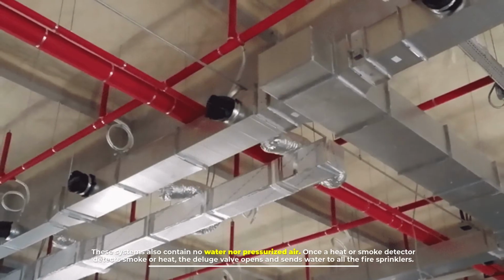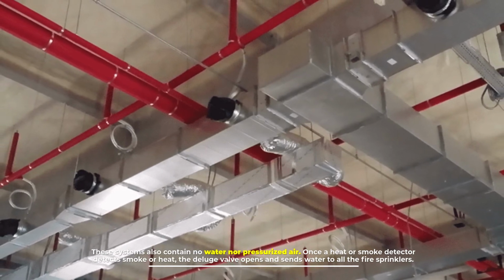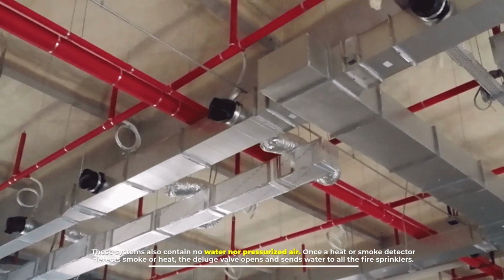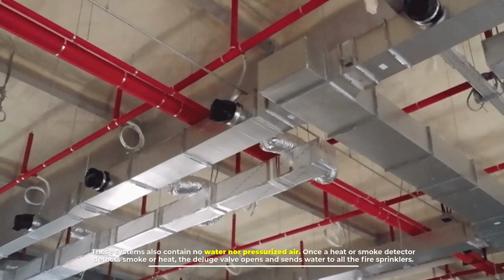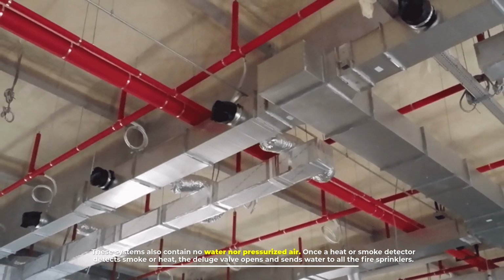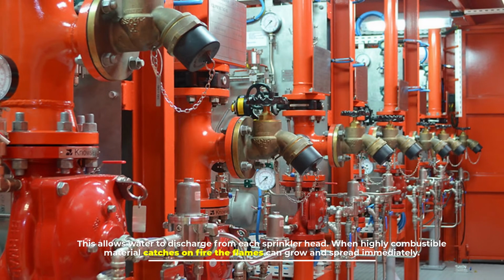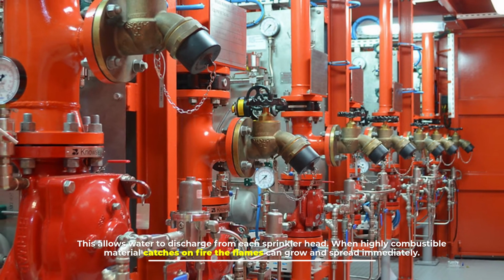These systems also contain no water nor pressurized air. Once a heat or smoke detector detects smoke or heat, the Deluge valve opens and sends water to all the fire sprinklers. This allows water to discharge from each sprinkler head.